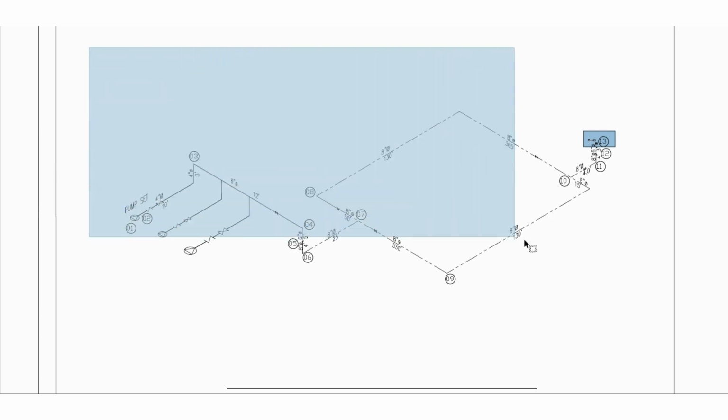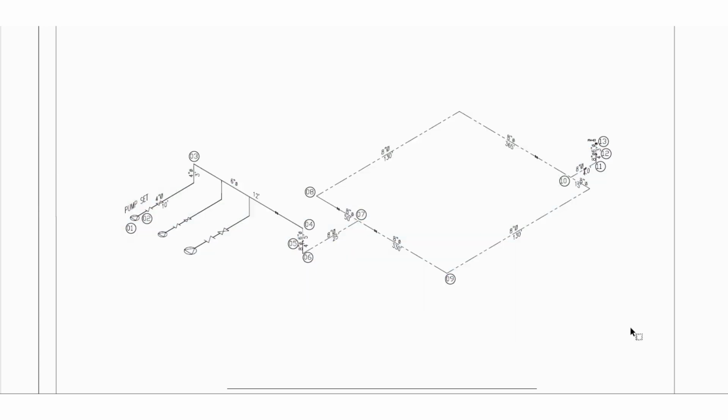For example, based on building code analysis, if your building requires 1000 GPM, then I will consider 1000 GPM from this particular hydrant. So the outlet from this hydrant will be 1000 GPM. But if I consider 2 remotest hydrants, then the flow from this hydrant will be 500 GPM and the other hydrant will be 500 GPM.